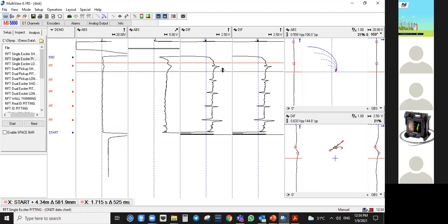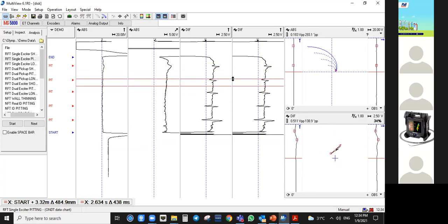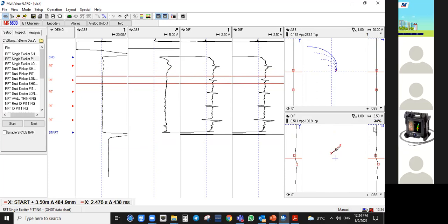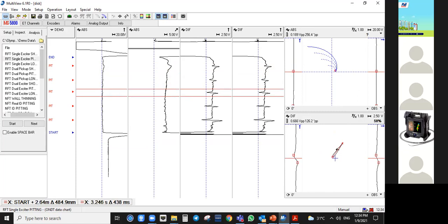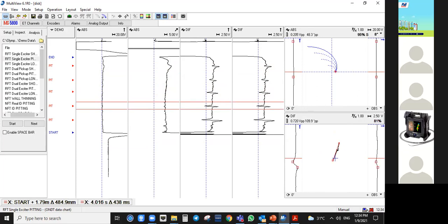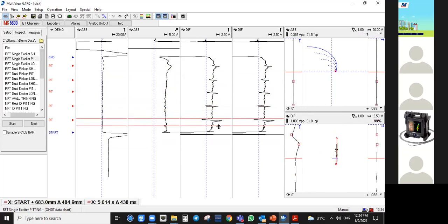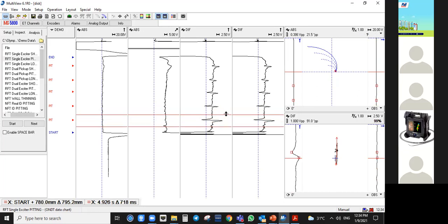This one is approximately 21%. Sorry, this one is 34 or around 40. This one is around 60%, flat bottom hole. This one is around 80%. And then remember the wizard setup, your hole should be 90 degrees. So this one is around 91. This is how we calibrate things, and after calibrating, we can start our inspection.